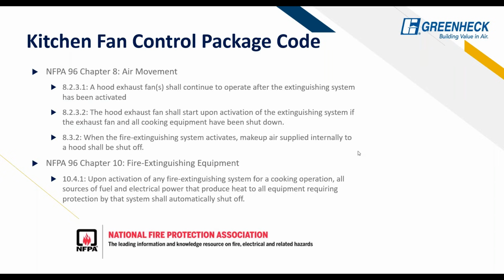So more on the codes here. This is just what happens in the event of a fire. Once the hood's fire system is activated, the exhaust fan shall go to 100%, and the makeup air should be completely off. That's something we have automatically in the package control. So it's nothing that you guys need to worry about too much, as long as you're specifying a package control system from your hood manufacturer. That should be no problem.